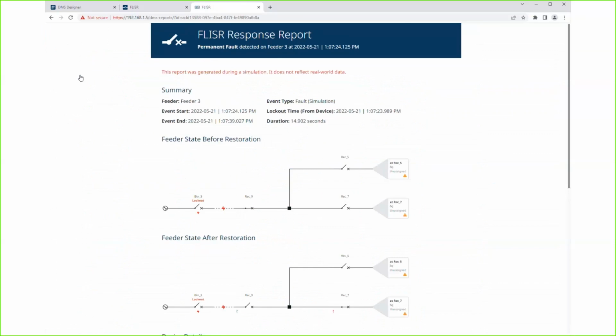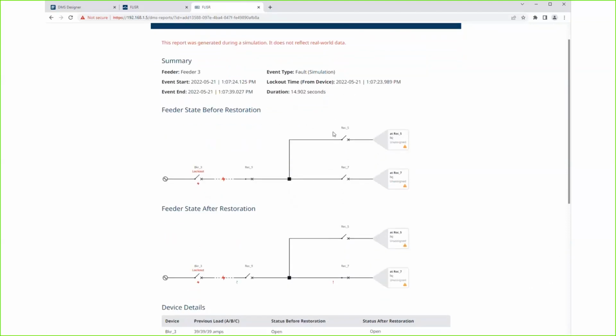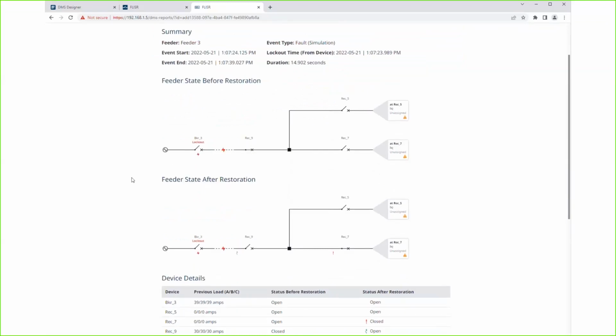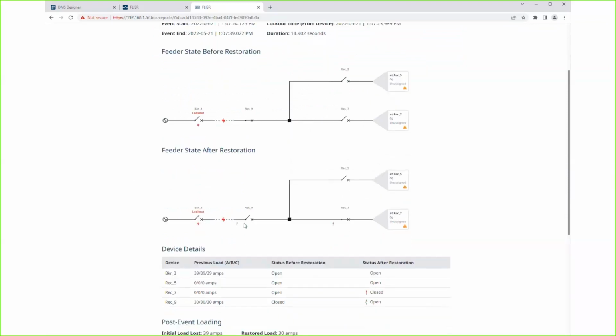Now here's the reporting part that we talked about on the first slide. If I wasn't watching, I should be able to come in and see what it saw and what it did. So where did the issue occur? What was the issue, so fault in this case? When did it happen? What did my feeder look like at the moment lockout occurred? And what did my feeder look like afterwards? An important note here is it's drawing in the report exactly what I drew in my settings. So if I didn't care about things being lined up, they wouldn't be lined up in here either.